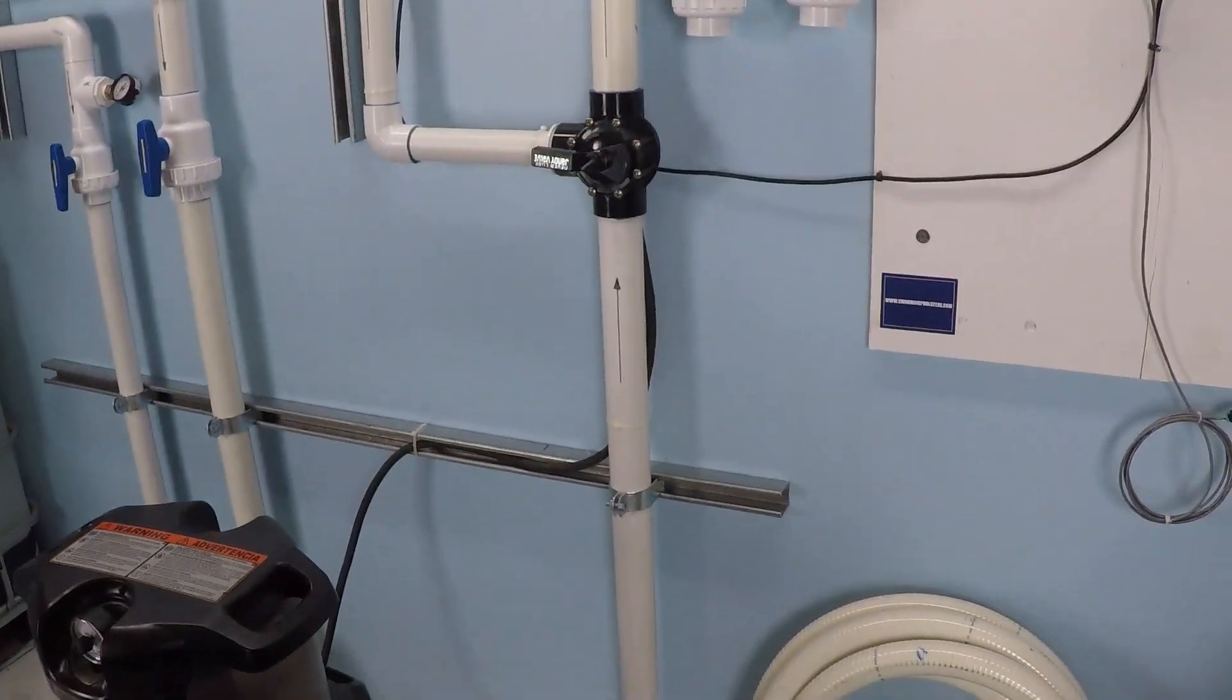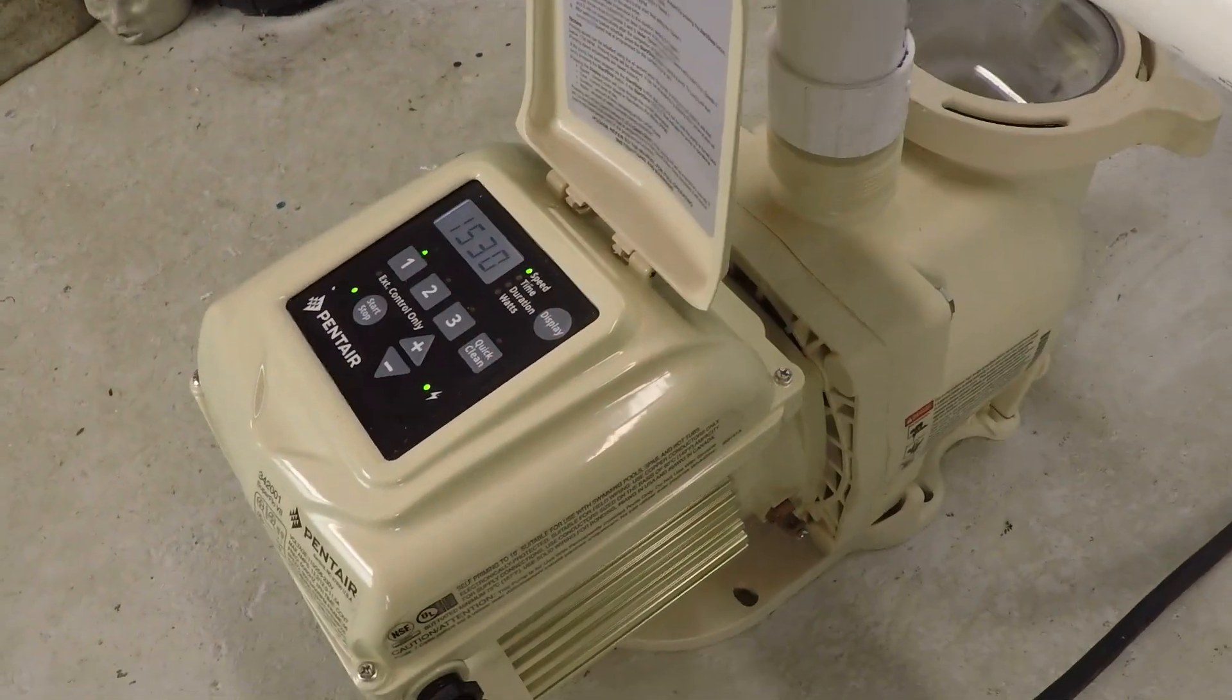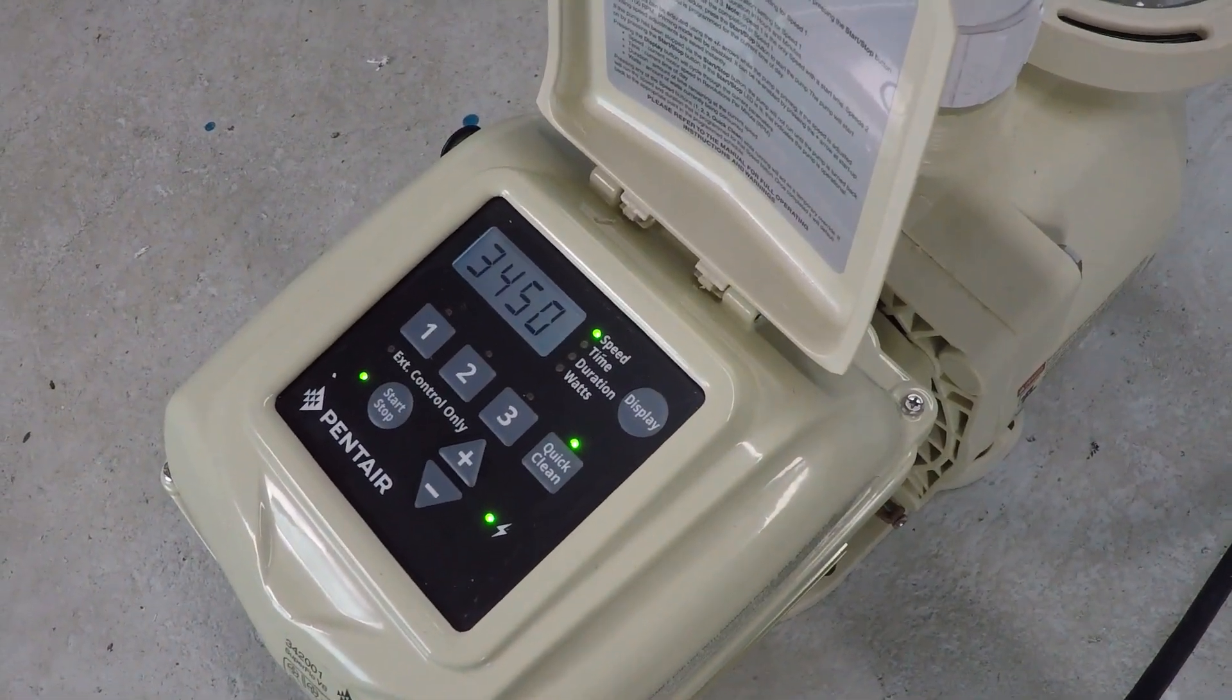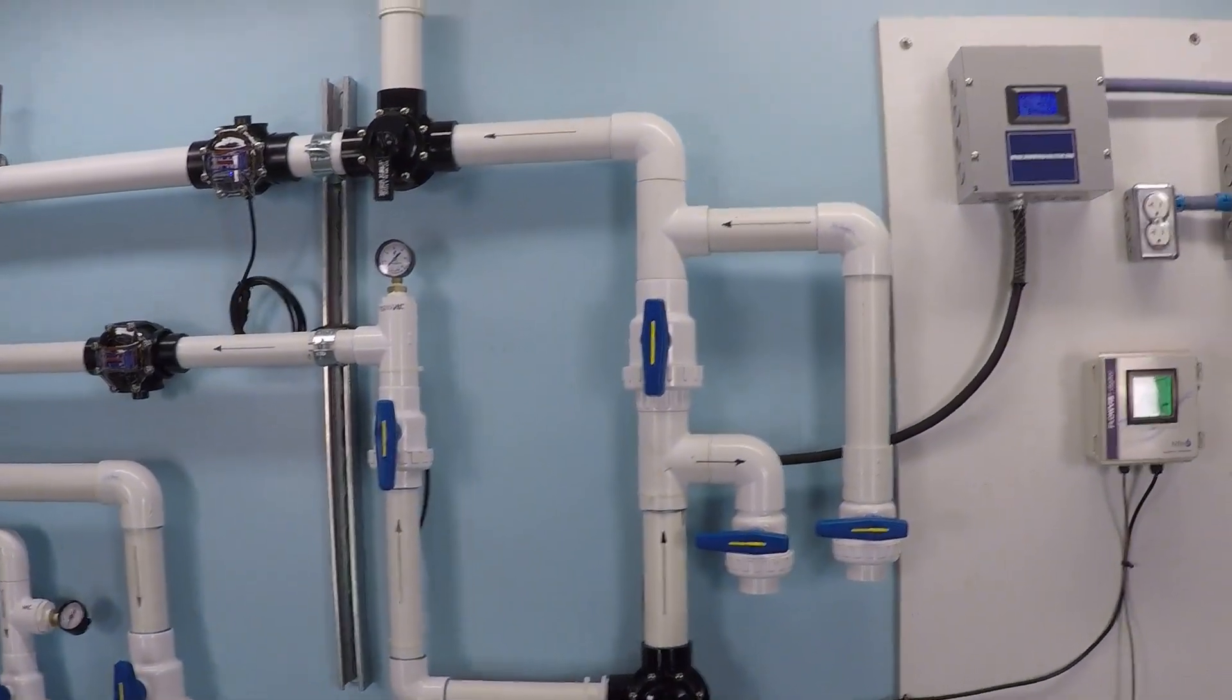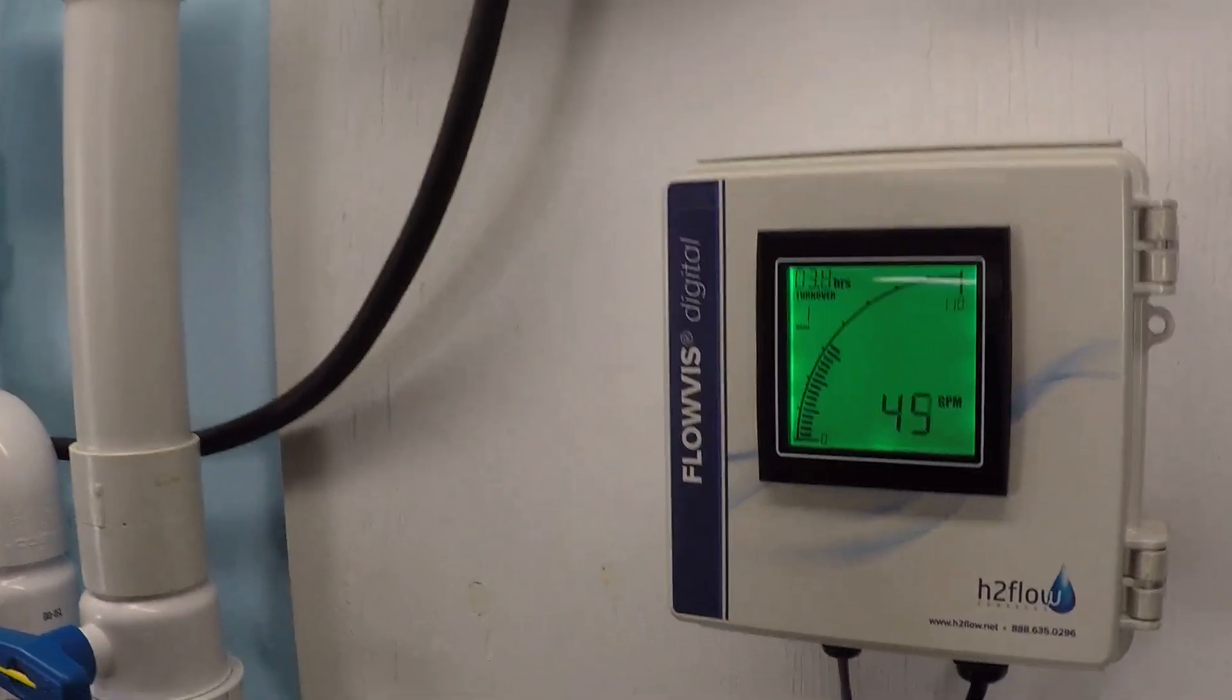However, here's something that I thought of recently. If you got a variable speed pump and you just did this, I'm just going to turn it on full speed and leave it like that forever, I'm so happy I got a variable speed pump, the savings are pouring in. If you do that, you're not going to save any money at all.